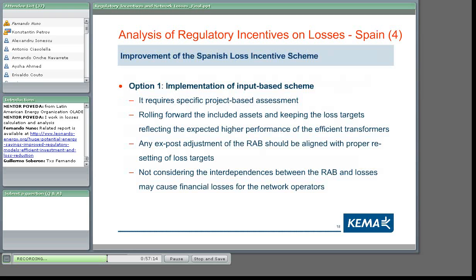Now let's put this in the context of the Spanish loss incentive scheme. If you go for the so-called input-based scheme, it means checking on the input side the equipment which can provide loss reduction, for example different types of loss reduction or efficient transformers. This requires a project-based assessment, case by case, where both the company and the regulator must check which equipment is really feasible to provide the expected loss reduction and is economically feasible. In this case, there must be a separate cost-benefit analysis for each of them.